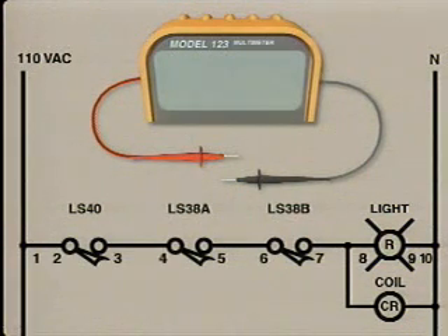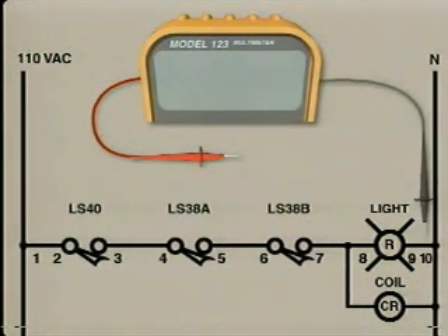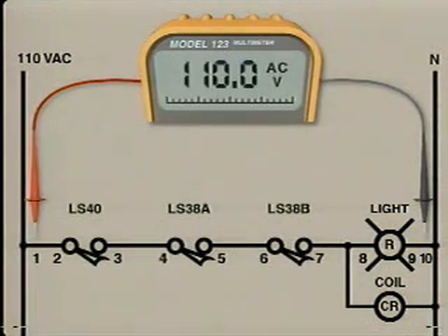To make it easier to follow the voltage test that the electrician will perform on the circuit, we'll number each test point. We'll use these numbers to refer to the locations that the electrician tests. The first test will be to verify that the circuit has the proper voltage. The electrician will use test point 10 as the reference point for all the tests, and he'll perform this test at test point 1. The voltmeter indicates full line voltage, so this circuit has the proper operating voltage.